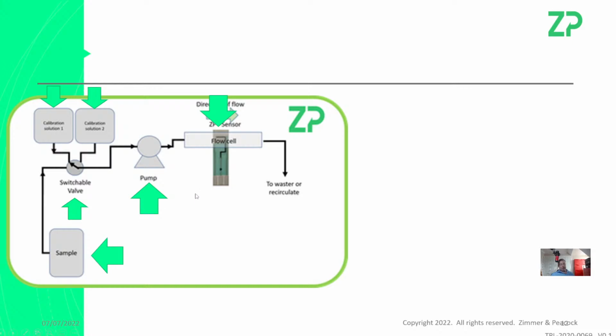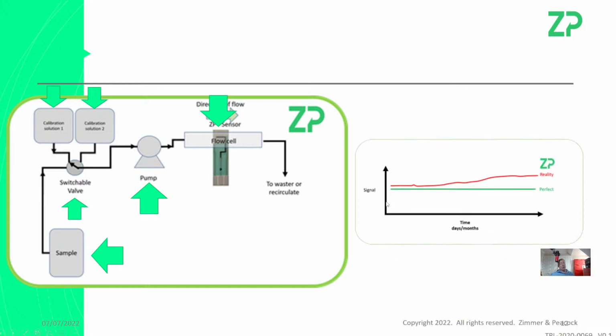And the reason I bring that up is because there's one thing that sensors, or biosensors, do: they drift. So the perfect signal is if the pH, for example, is stable, then obviously the signal is stable. But anyone who's used a pH sensor in the lab knows how often you're recalibrating them every time you use them. And it's because sensors drift. So the reality is sensors do this. When you have calibration solutions, like I've shown here, you can run calibration solutions periodically over the sensor and do a recalibration. What I'm describing here is the workflow for a product.